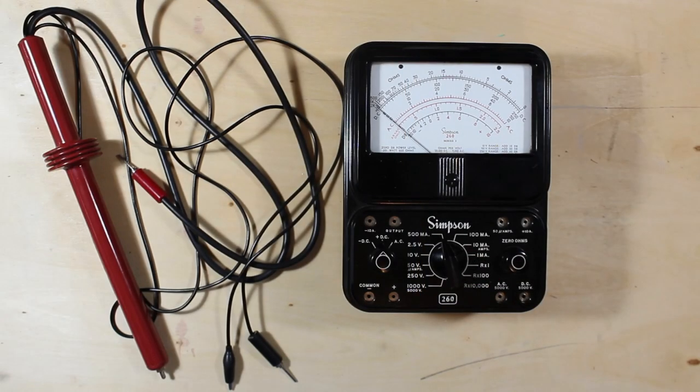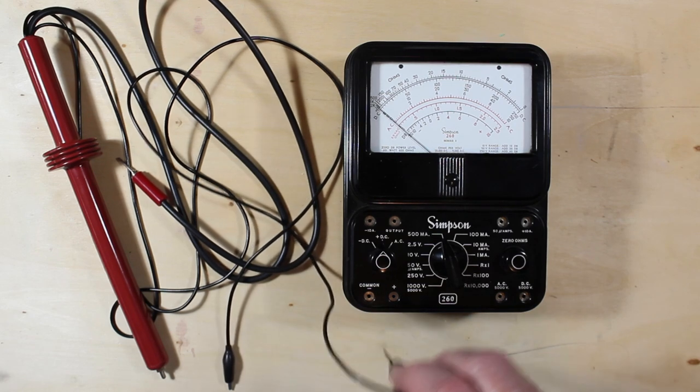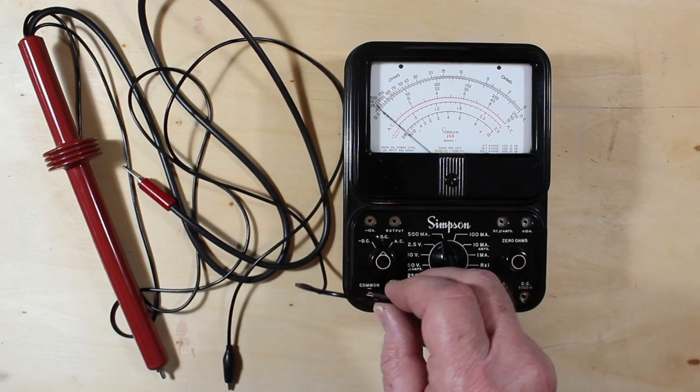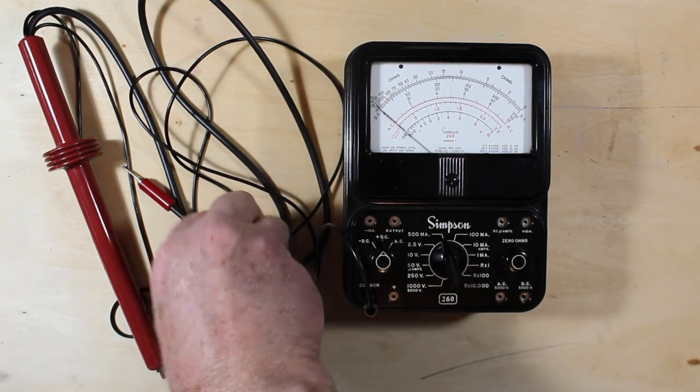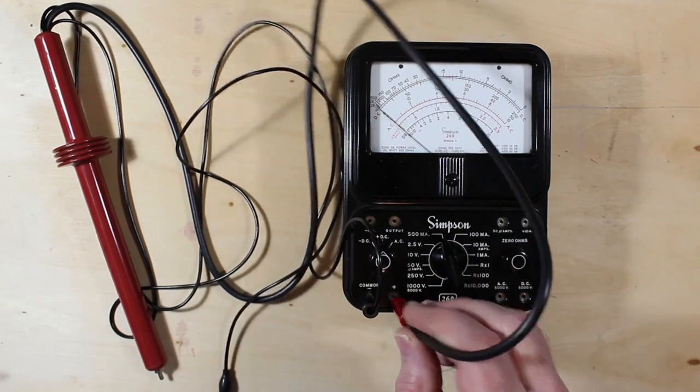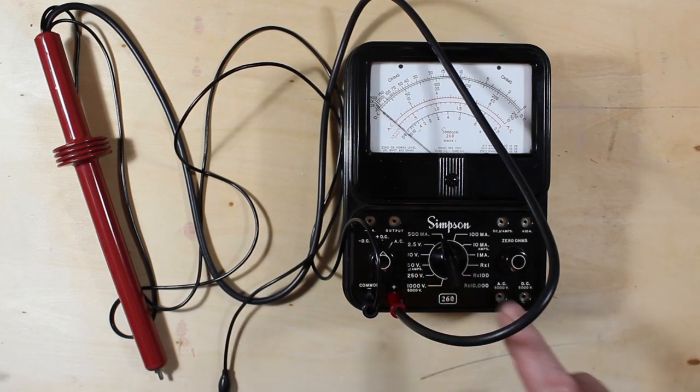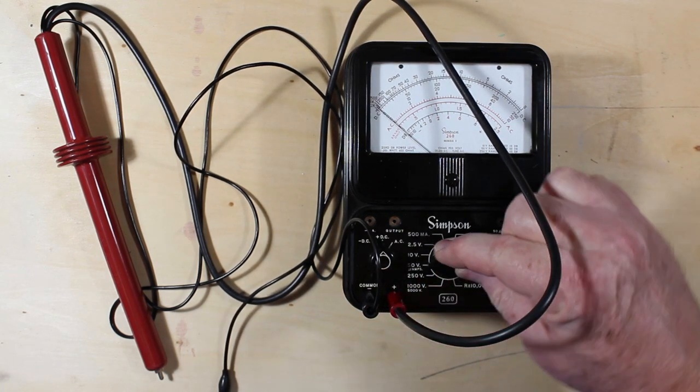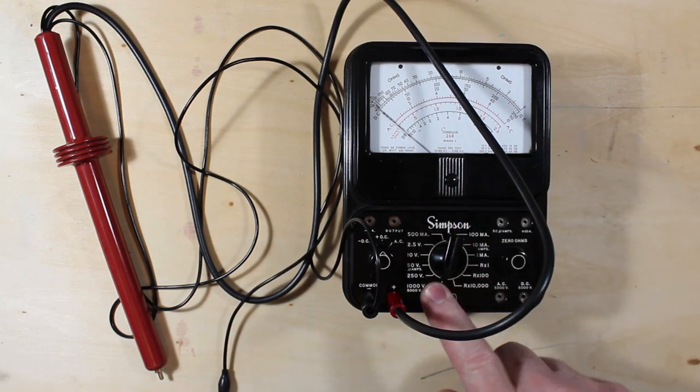So to connect the high voltage probe into the Simpson meter, you would take the negative black and hook that into the negative side. The positive lead, red here, hook that into the positive connection down here. Switch the meter to a 1,000 volt selection, right down here.